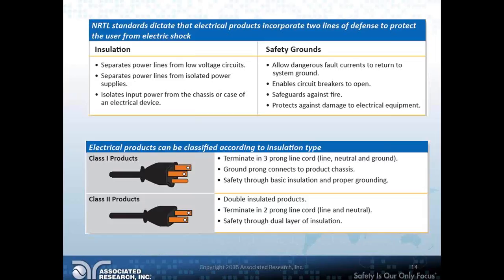Safety grounds allow dangerous fault currents to return to the system ground - that's what a safety ground is for. You want to make sure that if something does go wrong with the insulation, that current has somewhere else to go - not you, that's your safety ground. It enables your circuit breakers to open. It safeguards against fire, so that if you go beyond a certain amount of current flowing through a ground circuit, that's when your breaker trips, so it doesn't start a fire in your home or business or whatever the case might be. And it protects against damage to electrical equipment.